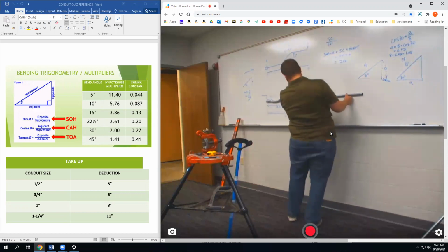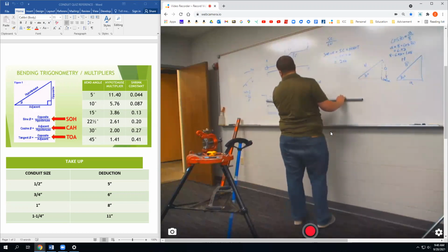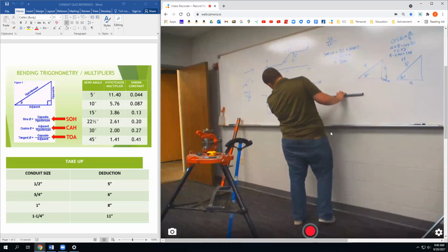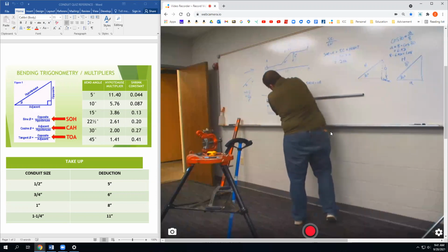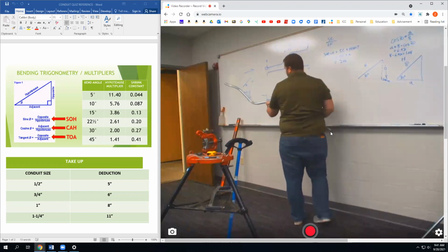Would that be less of a pain, to bend the second bend in from the left on the box offset up? Would it be easier to do that? I guess if it were going out, I could still do that. Let me line it up. You tell me. So what Garrett is saying is, can I take this one and bend it up a little bit more? It looks like I can, because I have to work with it there.